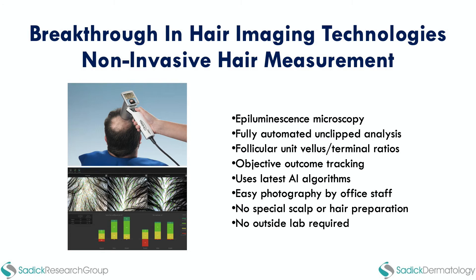This is a non-invasive hair measurement device that allows us to actually count hairs. Using a standardized zone five centimeters above the interglabellar area and five centimeters above the hairline, you get a hair density count for patients. Before PRP treatments, we can now look at the density of follicular units per square centimeter. It also tells you the number of anagen versus catagen versus telogen hairs, gives an index of growing hairs versus vellus-type hairs, and provides photographic evaluation with a computer readout. It takes about three minutes and is not expensive.